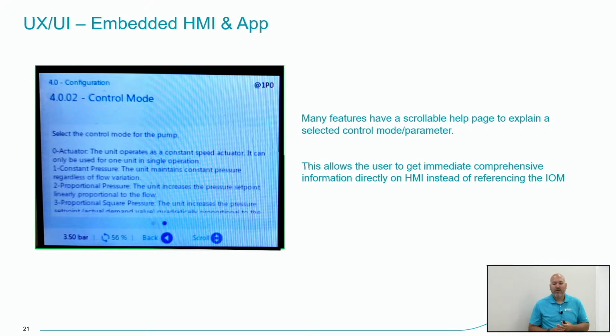So another neat feature, I like to call this basically like an embedded IOM inside of the Hydrovar X. As I touched on before, a lot of VFD manufacturers use different terminology for similar functions or capabilities. So you may not necessarily be familiar with everything in the drive, or if you're just a new user to the VFD, if you're not quite sure what something is, you have the ability to hit an info button, and it's going to give you a pretty detailed description of what exactly that function or feature will do for you. So you don't have to go digging through an IOM, call tech support, or anything of that nature to try to figure out what a control mode is. Like I said, there's simply an info button, and you get a pretty detailed description of what that said control mode or feature is.